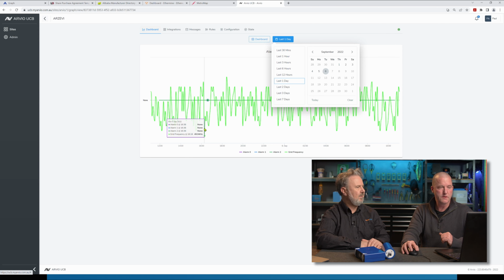All right. Okay, so if we go now to messages, you'll see the message triggers here. I set the window of tolerance to 49.99 and 50.01 hertz as the threshold because I wasn't getting enough alarms to see anything. So I set the window narrower to see it changing all the time, so I knew the rule was working. And then I just put it back to normal again. So you could then just use that to play in the FCAS market based on the settings that AEMO provide you with. Precisely.